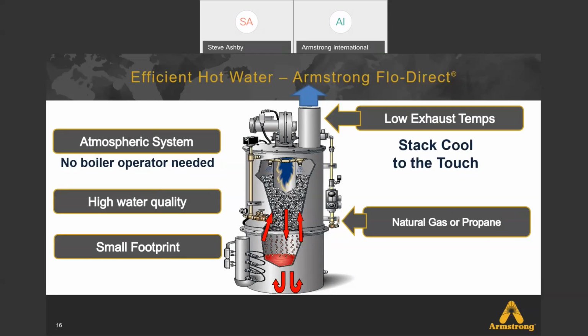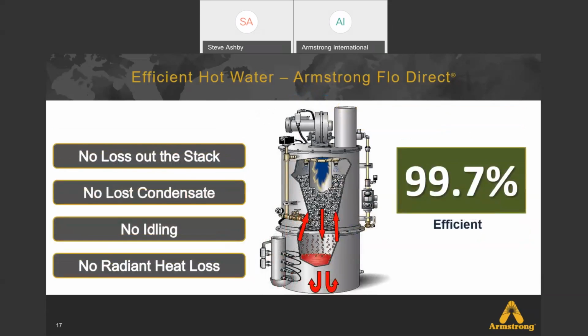Very low exhaust temperatures. That venting is cool to the touch. Gives you an idea of the efficiency that's taking place in heating the water. And you can fuel these with natural gas or propane. Some more features of direct contact heating. There's no loss out the stack. There's no lost condensate, no idling, and no radiant heat loss. Again, a conversation when comparing steam boilers versus direct contact heaters. And again, that's done at near 100% efficiency.